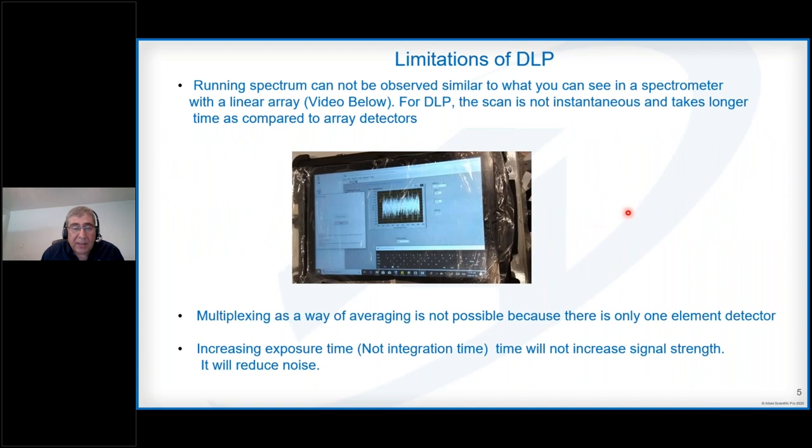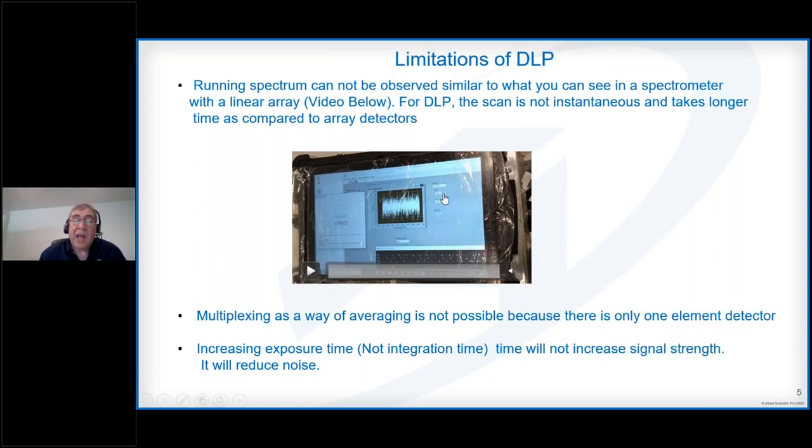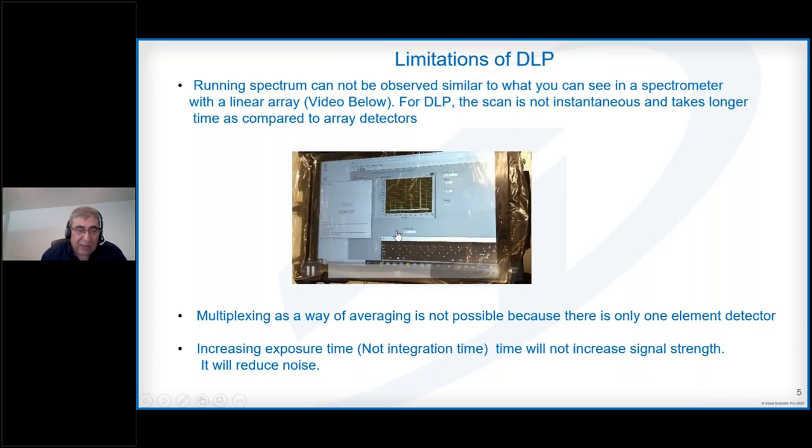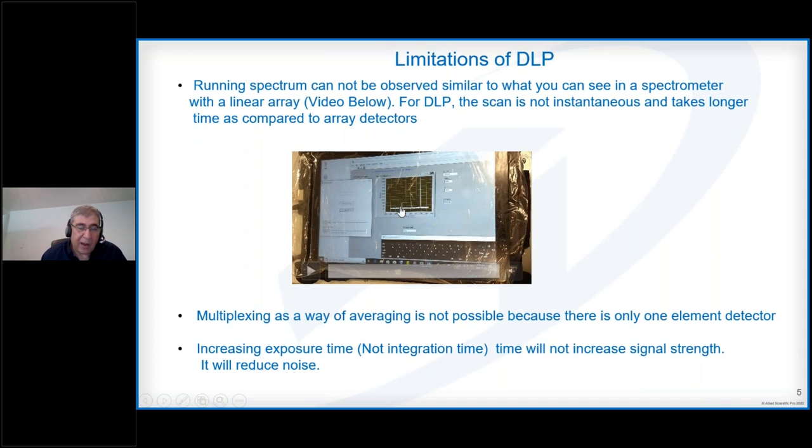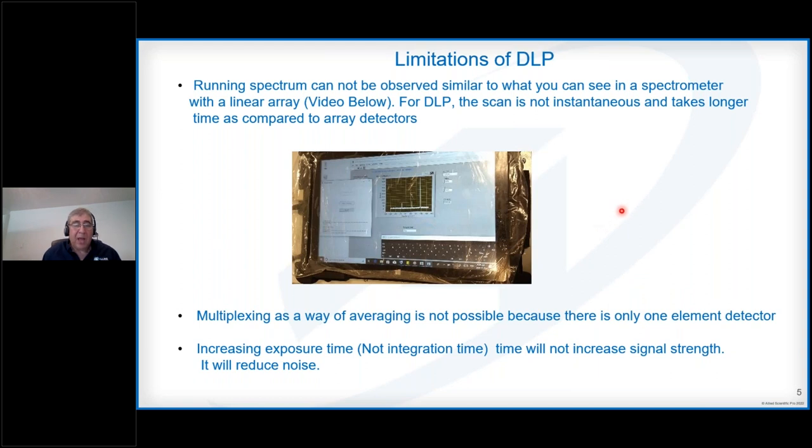Now, let's talk about the limitations. For this first limitation, I'm showing a video of a detector array spectrometer pointing towards a fluorescent lamp and it instantaneously detects the spectrum. As soon as it points towards the fluorescent lamp, it detects the mercury lines. The detection is instantaneous, and this is a good advantage for linear array. In case of DLP, this detection is not instantaneous because you're going bit by bit. You'll get a final snapshot of the spectrum. This is one limitation.